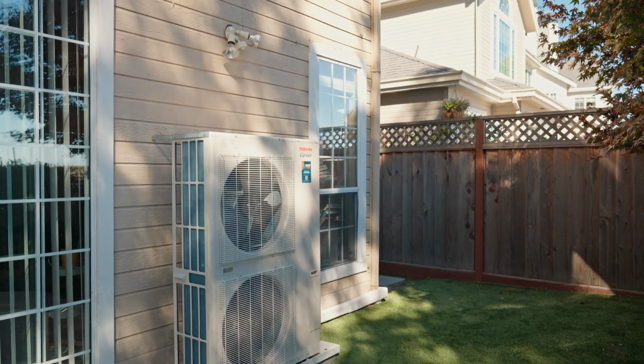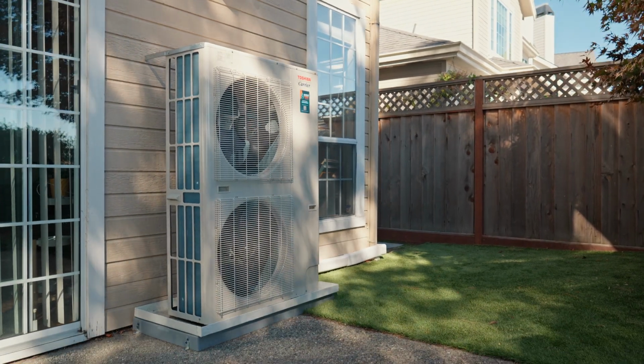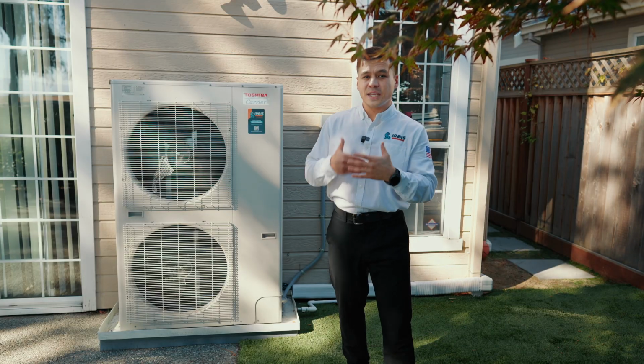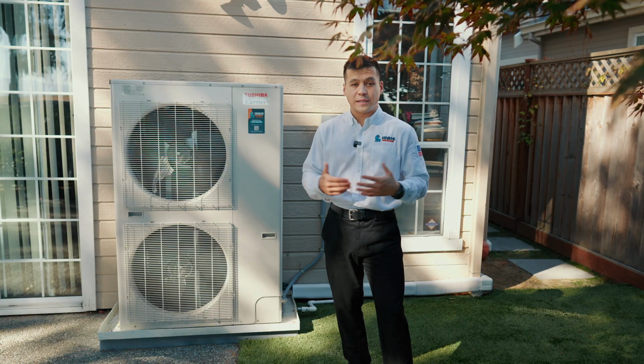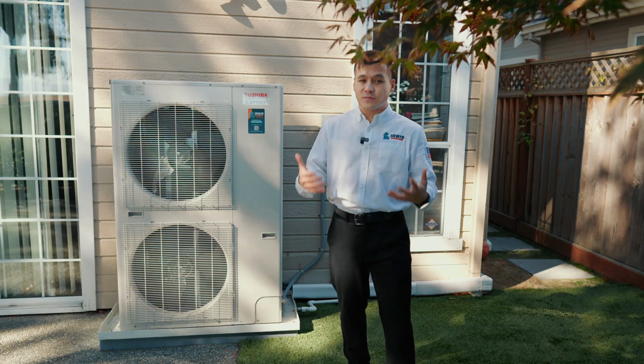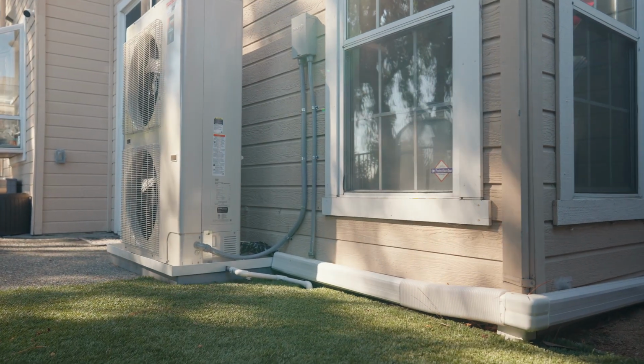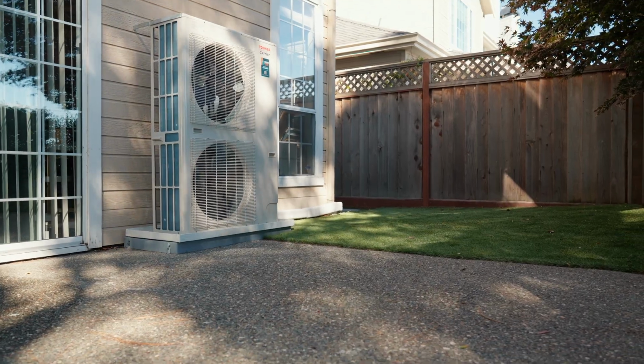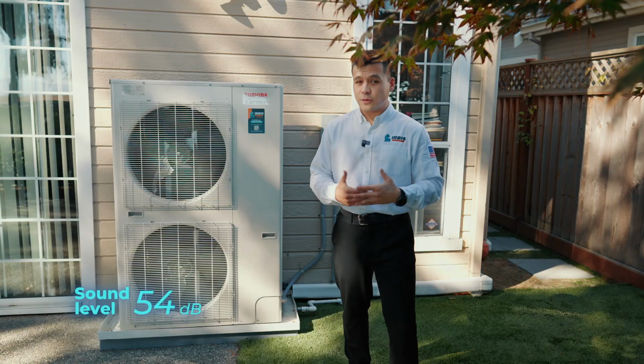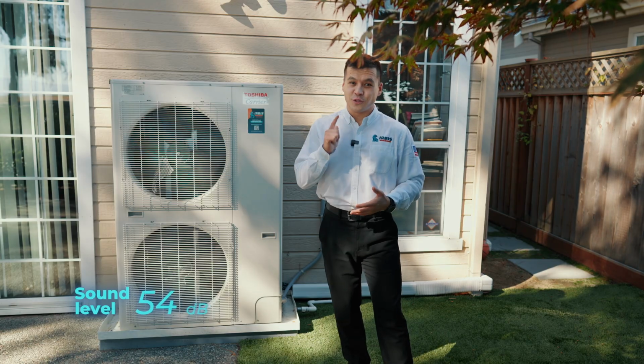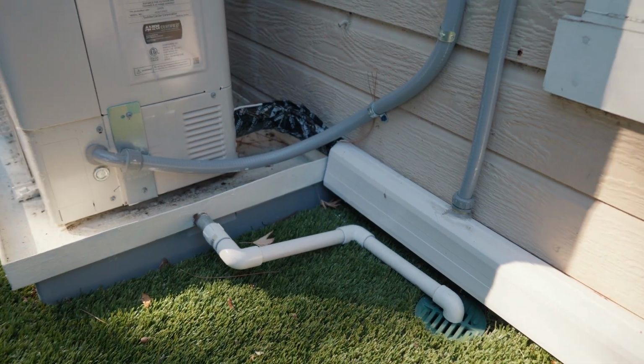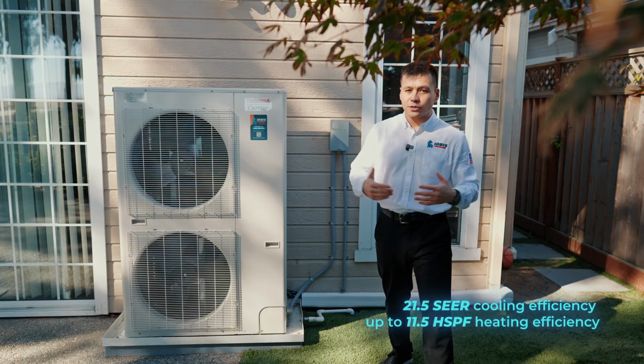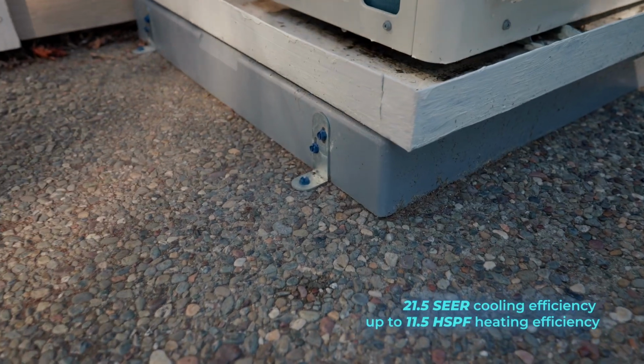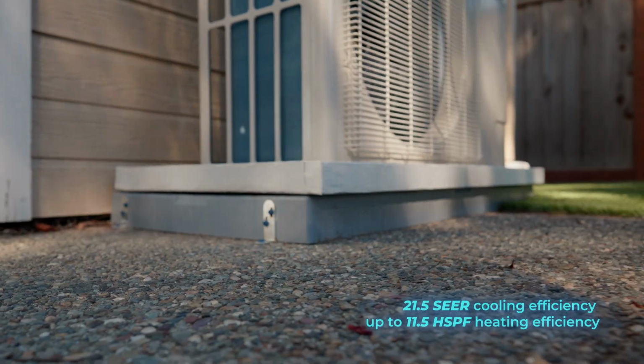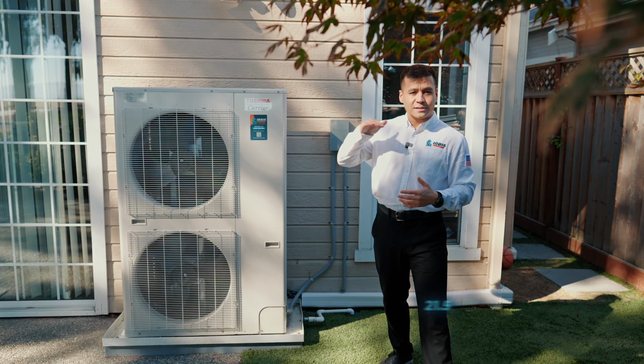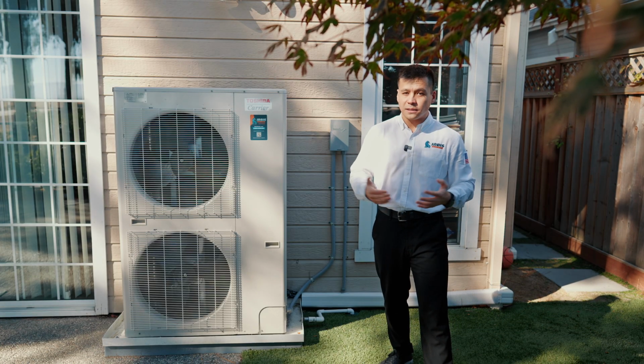So the inverter part means that the system doesn't turn on and off. It consistently adjusts its power capacity depending on heating or cooling needs. This feature provides more energy efficiency, and this system is super quiet, only 54 decibels of sound, which means it's quieter than a normal conversation. This system provides 21.5 SEER of cooling efficiency and 11.5 HSPF of heating efficiency, which is one of the highest numbers you can find across all the heat pumps.